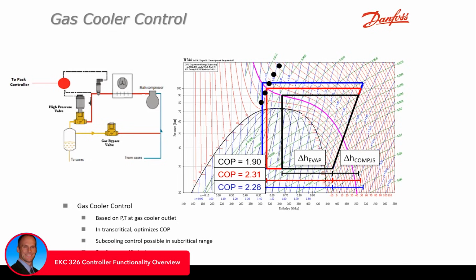Okay, and that's a big thing because a lot of people ask me how a controller really works. Nowadays you have your transcritical zone or mode, your transition mode, your subcritical mode, and then your low pressure mode. This is what's built into the algorithms of the controllers, and this is really what has evolved over the years.